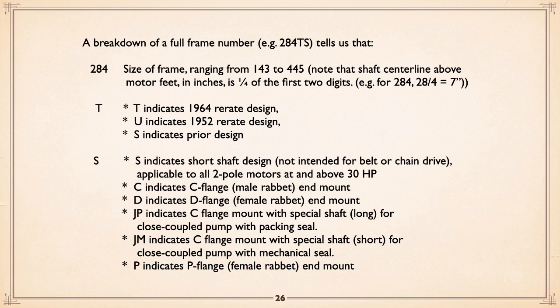JP, as I mentioned before, has a special long shaft for close coupled pumps with packing. JM has a much shorter shaft for close coupled pumps with mechanical seals. P indicates a P flange, which is a female rabbet, end mounting. It's the P base that vertical turbine pumps use. In fact, they're very often referred to simply as P base motors.